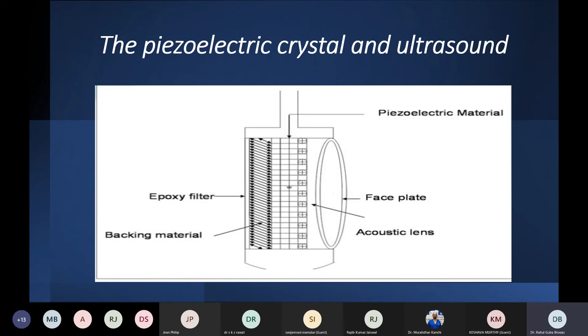Now, this part is very important for us to understand. What happens when a piezoelectric crystal goes out to the human tissue? Now, we are interested basically with getting back most of that sound wave back to the transducer as a reflection. And whether the sound wave will nicely get reflected like in a mirror, excellent mirror, whether it will get reflected or not depends on something called acoustic impedance. So based on the acoustic impedance, if a desirable difference in the density from where the sound is going to which tissue the sound is hitting is there, we will get a nice kind of a reflection, and we will see all the structures in our field of interest.